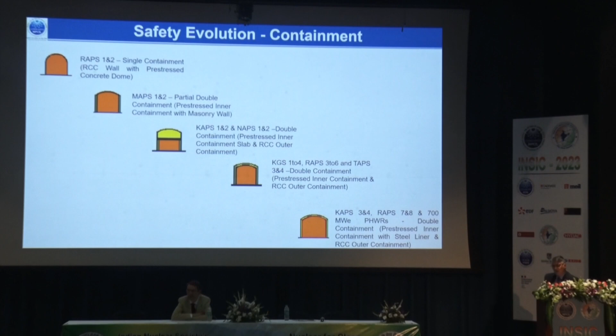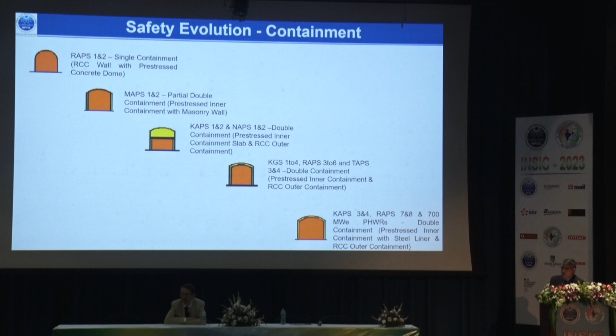Containment is very important in case of any reactor. So we have graduated from RAPS 1 and 2 to KAPS 3 and 4, the latest reactor, where we have a double concrete dome, and the inner dome is lined with a 6mm steel liner, ensuring the leak-tightness of the reactor building. We have implemented various systems, and that is why we could reduce the exclusion zone from 1.5 kilometer from the center of the reactor to 1 kilometer in case of the 700 megawatt design. Though the reactor size is large, we are working to reduce this distance further, so that issues related to land acquisition can be resolved to some extent.